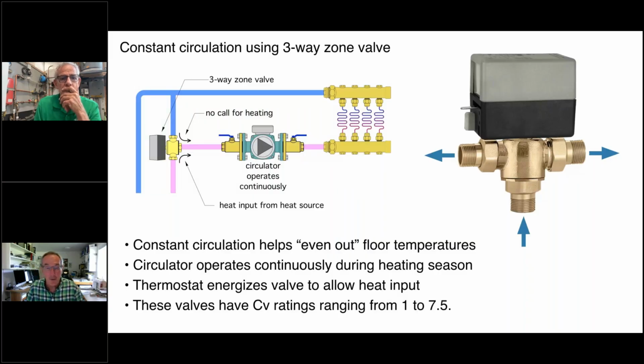And just a couple of cautions. These are basically three-way zone valves. They go up to a CV rating of 7.5. So you could use these in systems where you have, I would say, up to maybe 8 gallons per minute, something like that. But when you get up into a big system, if you're trying to move 25, 30 gallons per minute, don't do it with this valve. The CV rating simply isn't high enough.